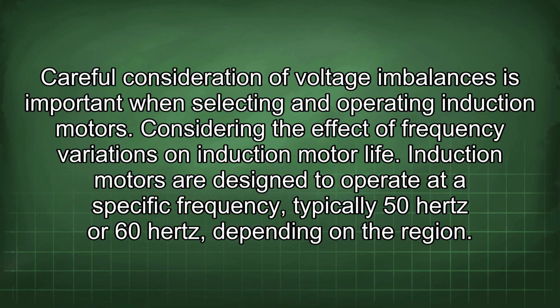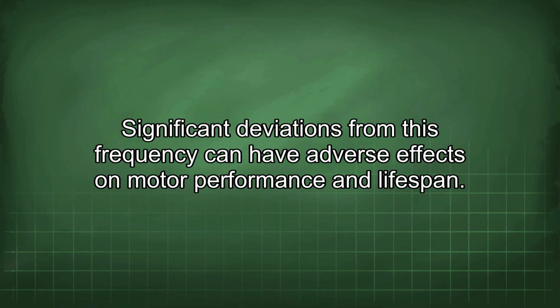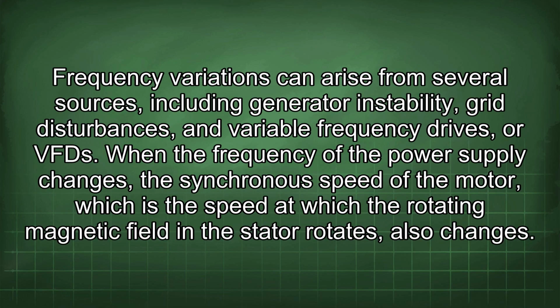Considering the effect of frequency variations on induction motor life. Induction motors are designed to operate at a specific frequency, typically 50 Hz or 60 Hz, depending on the region. Significant deviations from this frequency can have adverse effects on motor performance and lifespan. Frequency variations can arise from several sources, including generator instability, grid disturbances, and variable frequency drives, or VFDs.